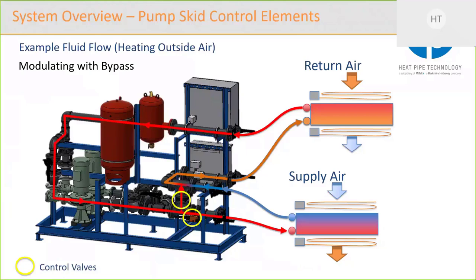control valves. Now, one interesting thing on our system is that we don't use a three-way valve. We actually use two inline valves. And the reason for that is that that means that we can de-link the relationship between bypass and inline resistance. So as the system curve moves around for different conditions, we can actually play with that. We don't have to follow just the set curve from a three-way valve.